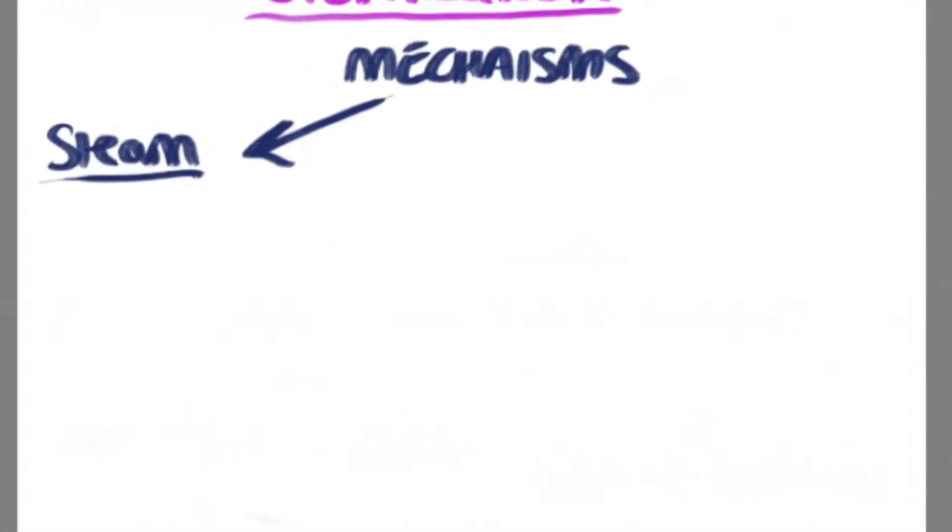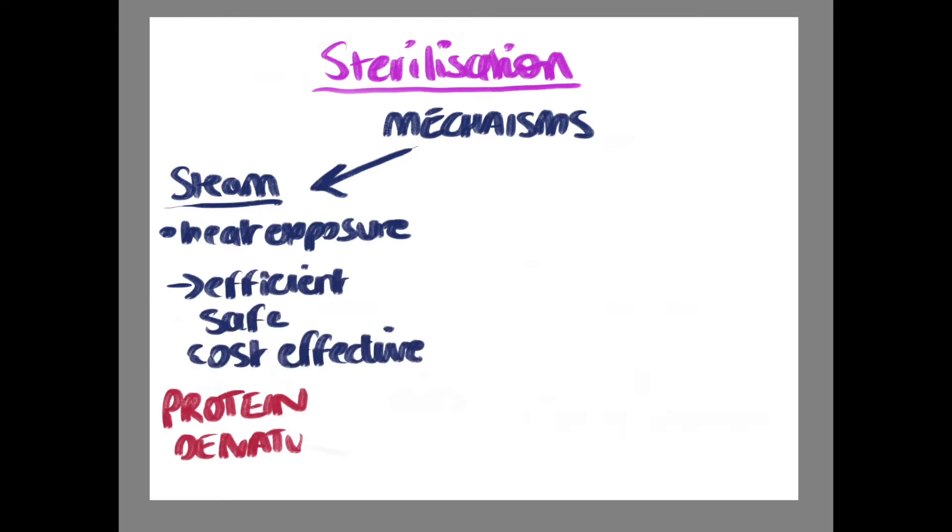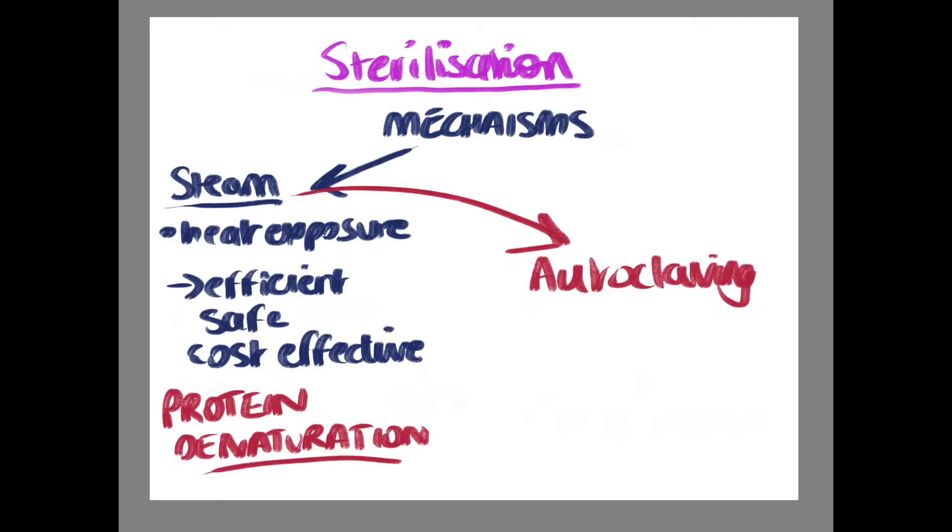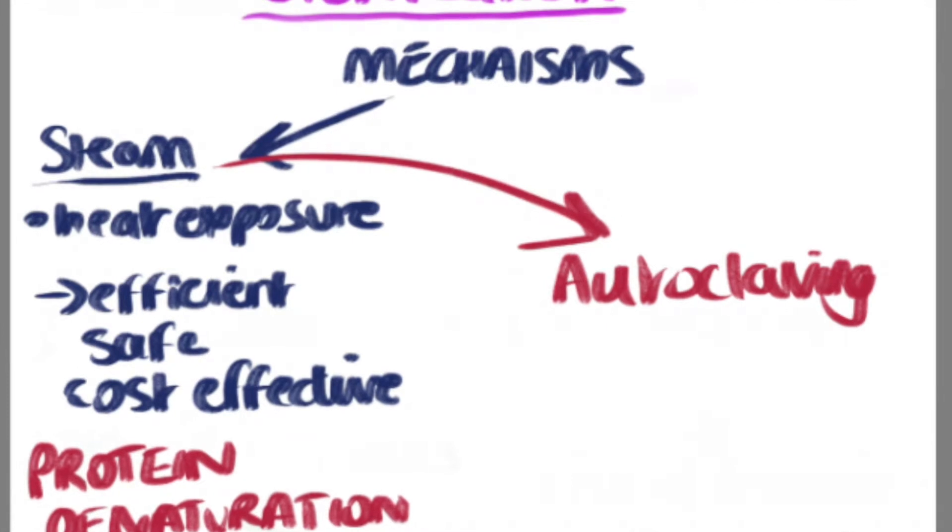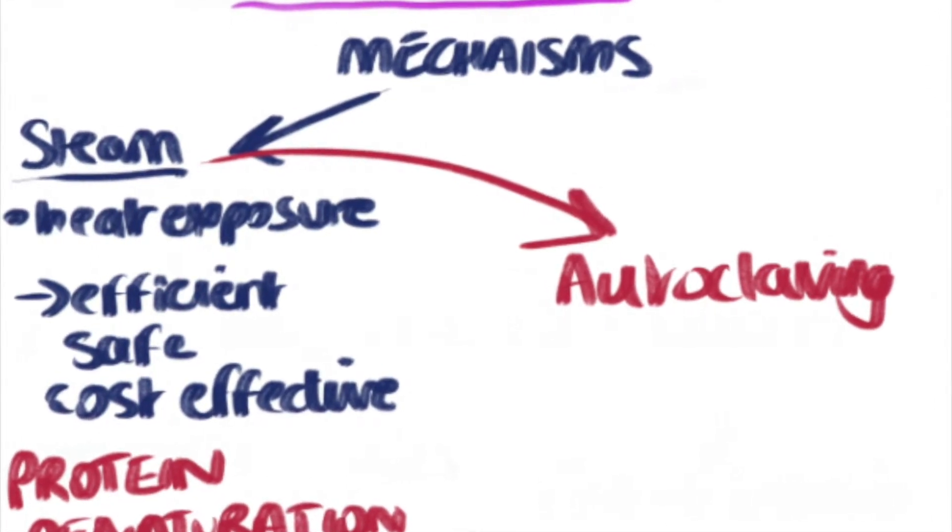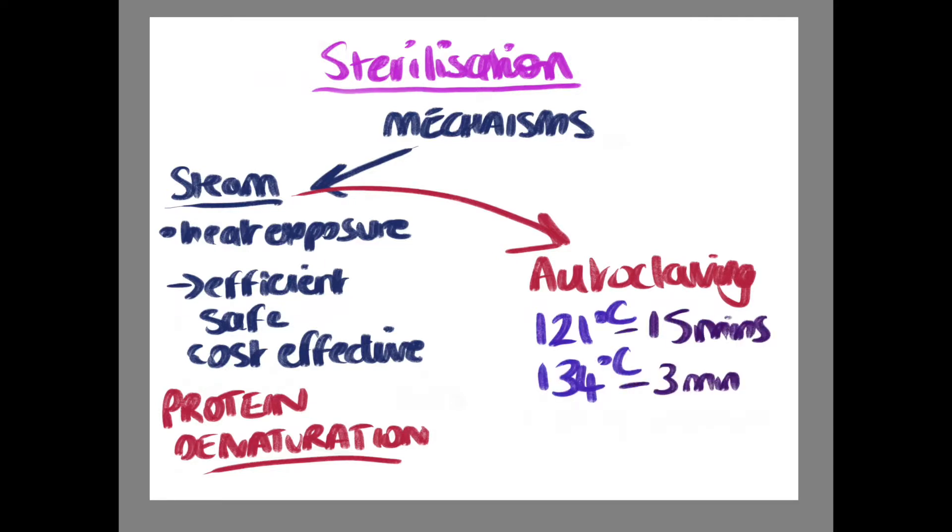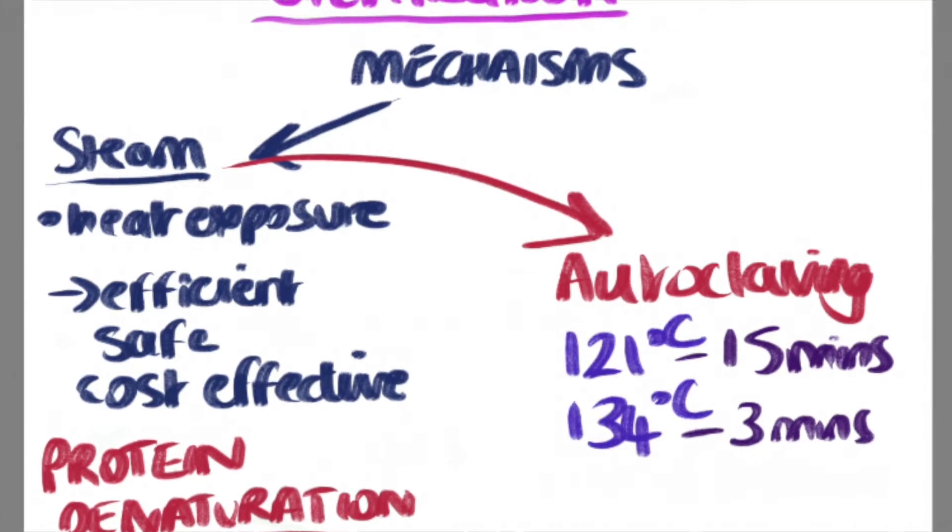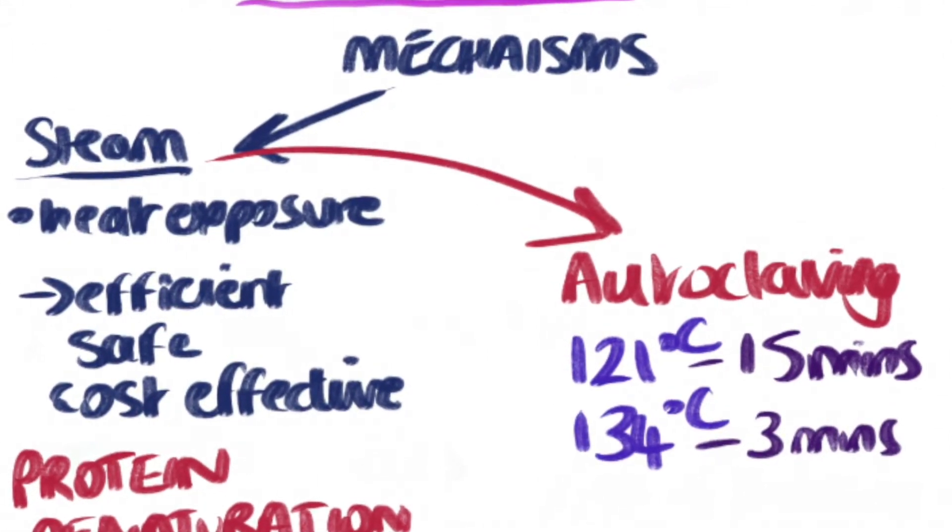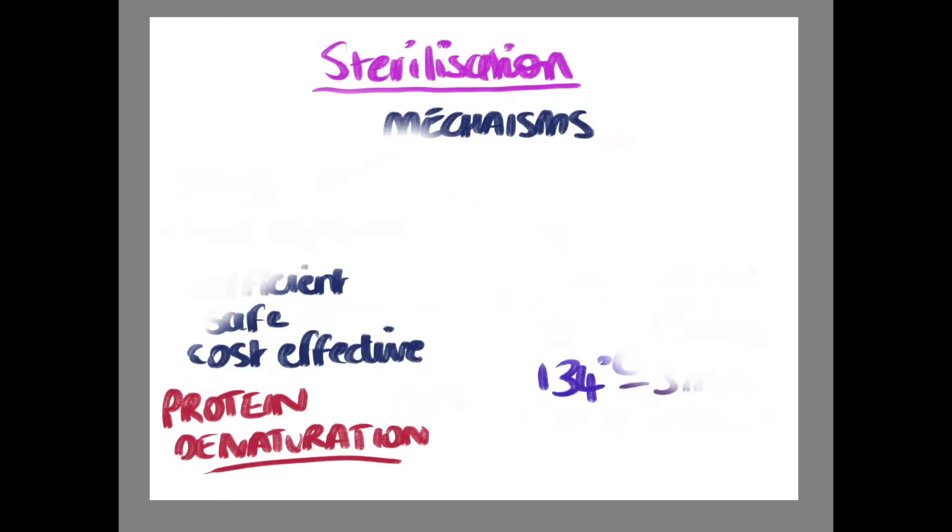Steam: If the equipment can withstand exposure to heat and moisture, then this is an efficient, safe and cost-effective method. Microorganisms are destroyed by protein denaturation. Autoclaving makes use of steam. This is essentially a pressure chamber which combines increased temperature and pressure for a certain time limit to achieve sterility. The most common temperatures are 121 and 134 degrees Celsius. The higher the temperature for a longer period increases the probability of sterility. The minimum cycle times for each temperature are 15 minutes and 3 minutes respectively.